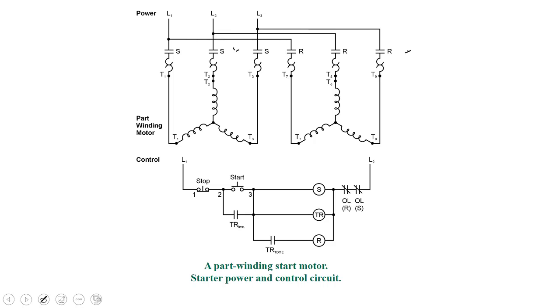Let's follow our little diagram here. What would happen? I press the start button down. Relay or coil S energizes, so that would close all these contacts right here. What else gets energized? The TR relay, so the timing relay. And you see that we've got instantaneous contacts here. They would close, so that forms the holding circuit.